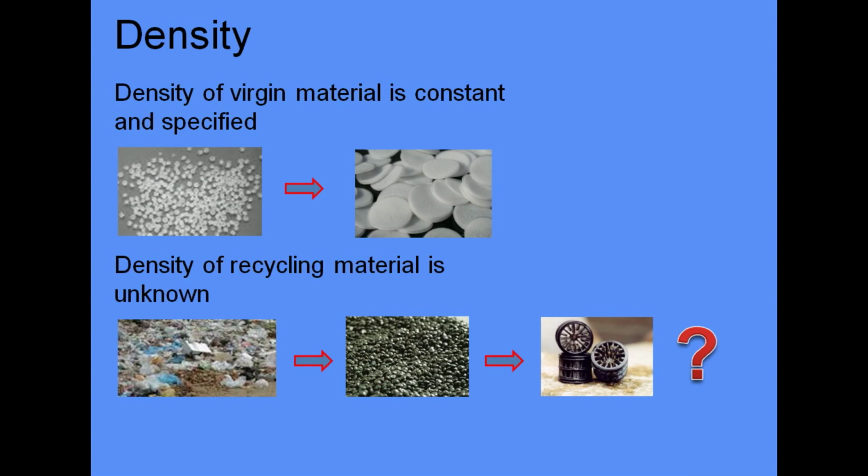You did mention the density of the material. Yes, the material density is important because it determines whether the carrier can be kept in suspension or not. That means it determines whether the carrier is floating or sinking to the bottom of the tank. And normally you should have a well-mixed tank, shouldn't you? Yes, definitely. And therefore, a constant and controllable material density is very important, at least from a productional point of view. Are any indications about the density for sponge-type carriers adequate? Actually not, because in that particular case, special procedural know-how is required.